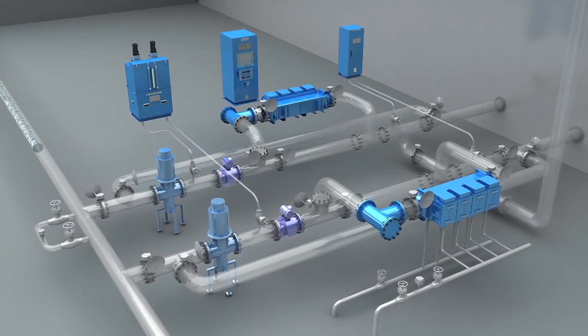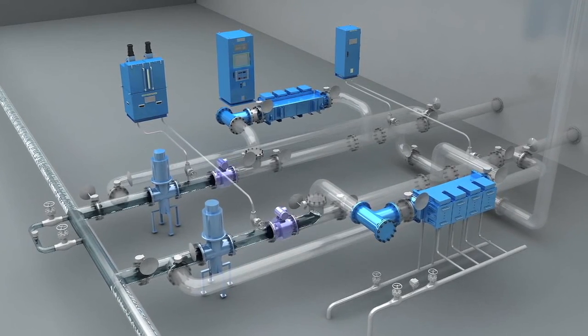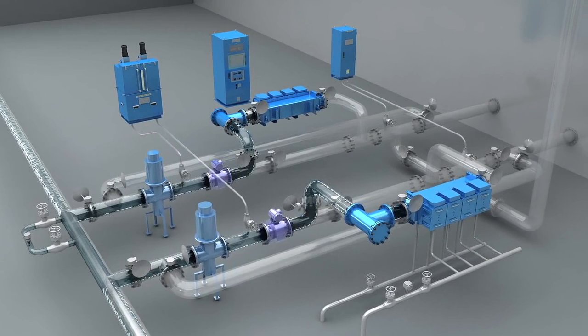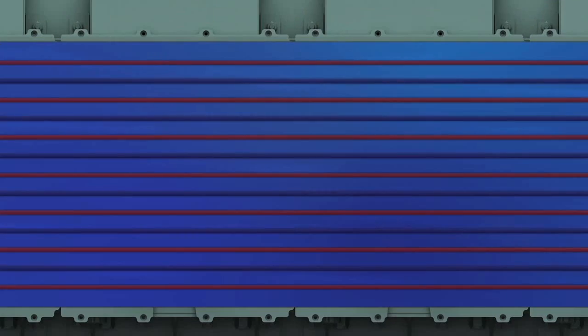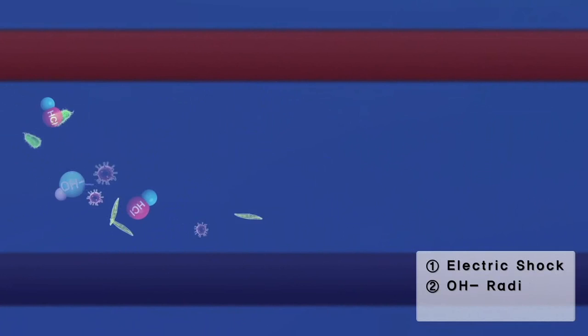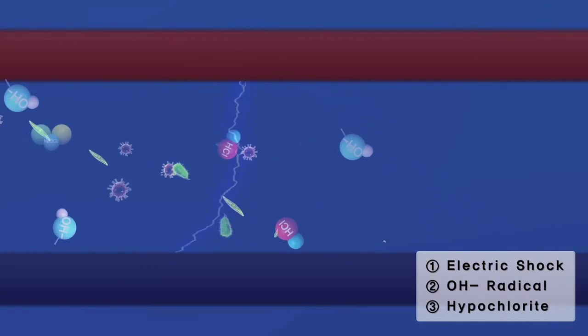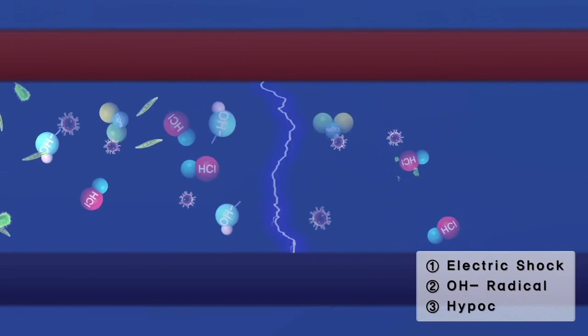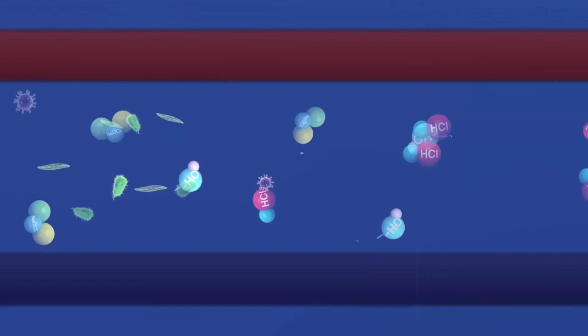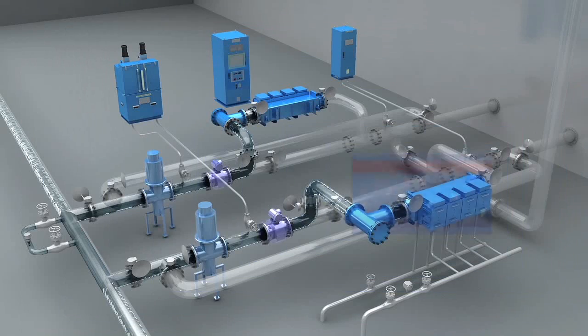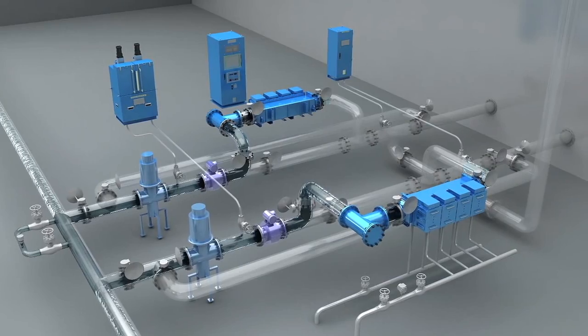ECU is used as the ballast water flows in the vessel. ECU receives the required current and voltage from the rectifier, enabling them to electrolyze the ballast water and kill microorganisms by electrochemical actions. The electric energy and the production of oxidants such as hydroxyl radical and hypochlorite oxidize cell membranes and cell walls to disinfect organisms.